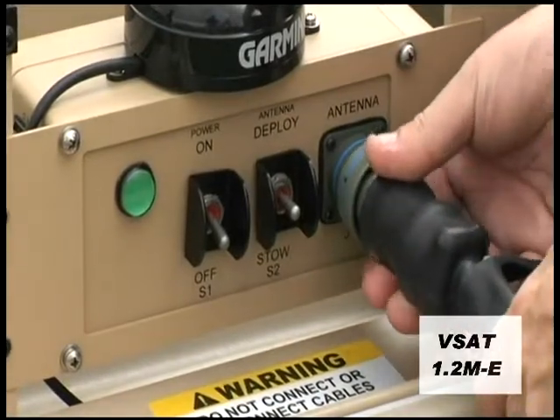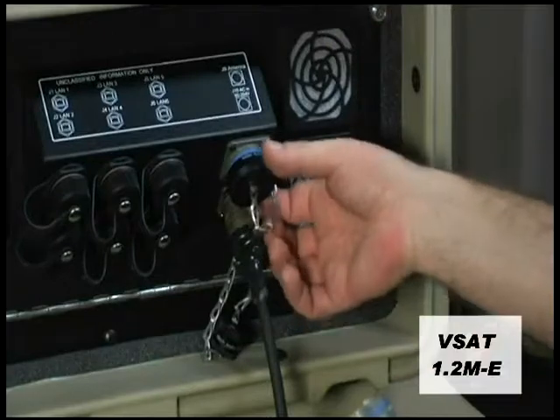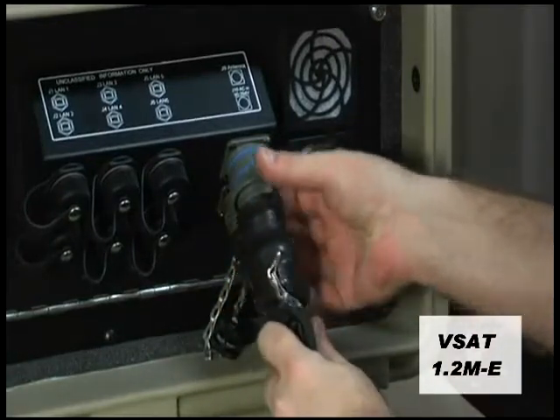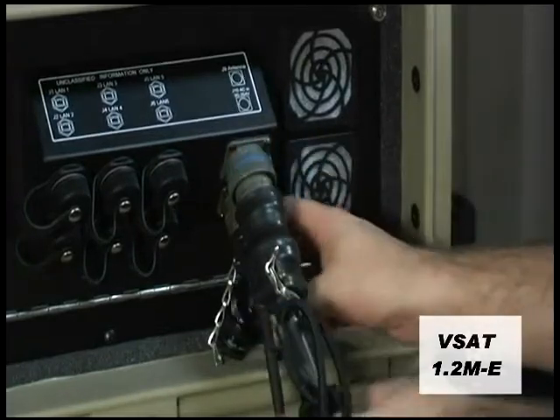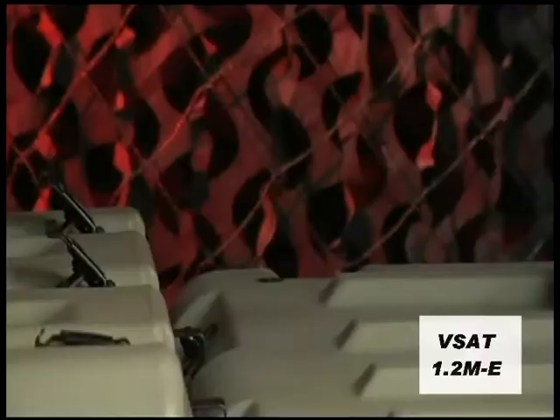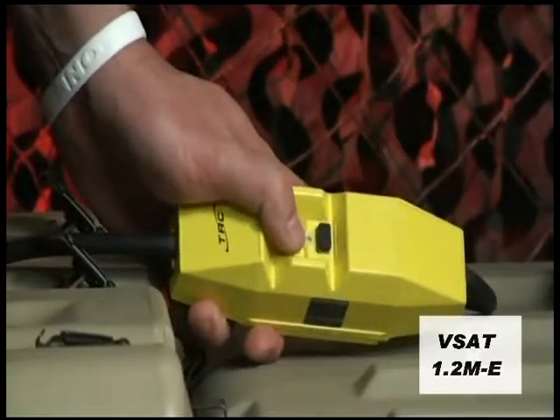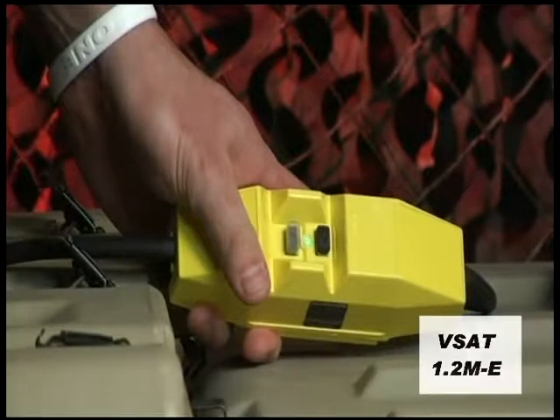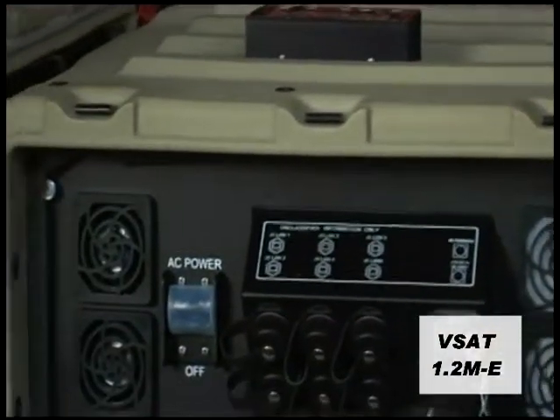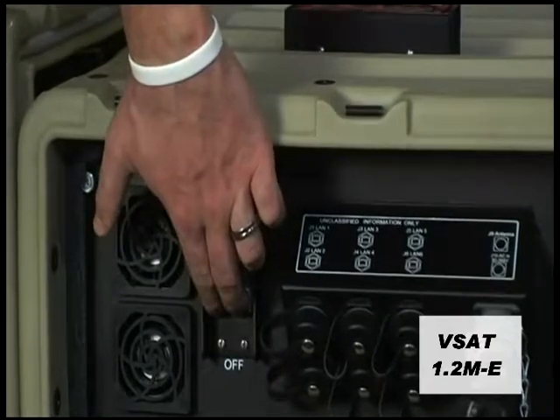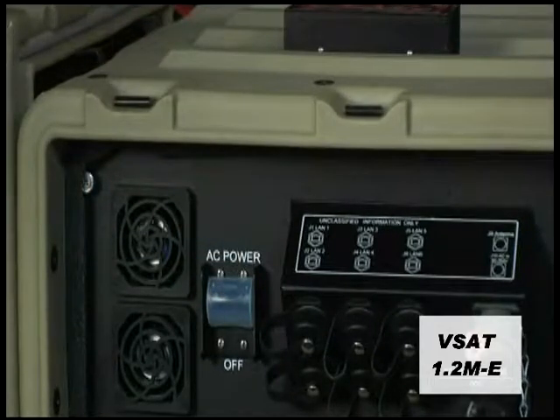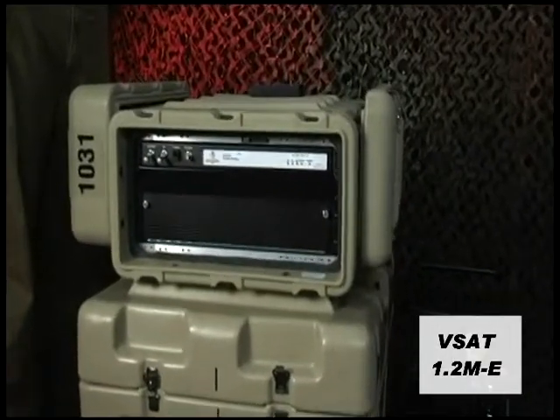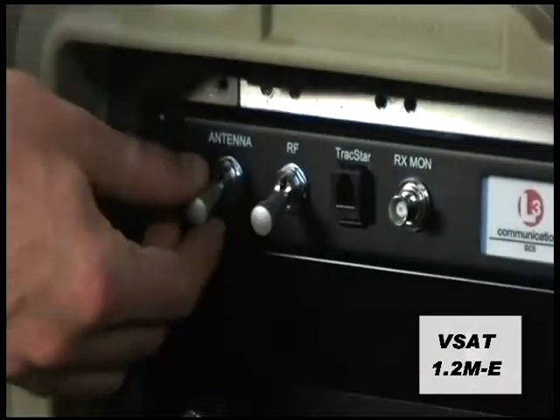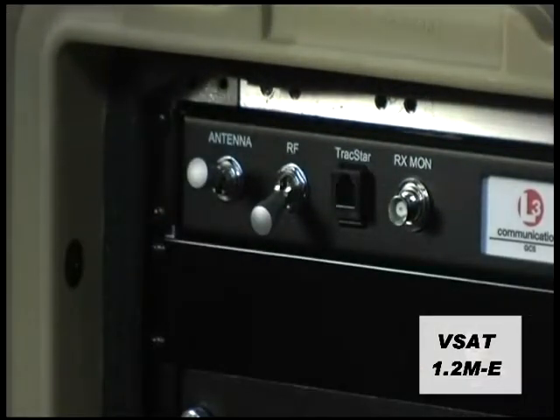Make sure to never connect or remove the cables with power applied. Connect the antenna side interfacility link or IFL cable to the control box. After connecting to a suitable AC power source, press the reset button on the AC power cord GFI box if the green LED is not lit. Now turn the AC breaker on the rear panel of the indoor equipment case to the on-up position. Make sure that the rubber protective cover does not interfere with the lever. Turn the antenna power switch located on the front panel to the on-up position. These switches are of the locking type and must be pulled out slightly to move their position. Leave the RF power switch off at this time. Then head to the outdoor equipment.